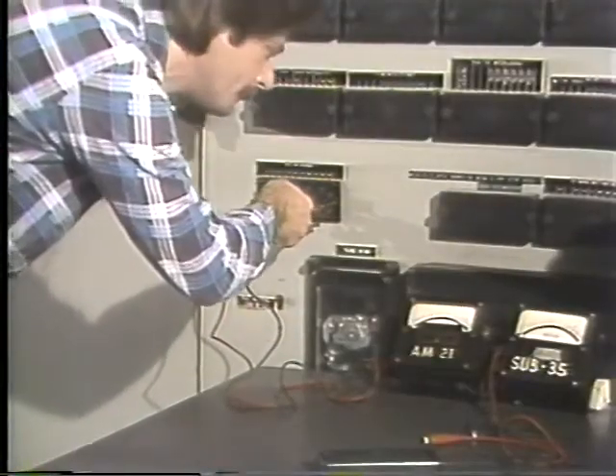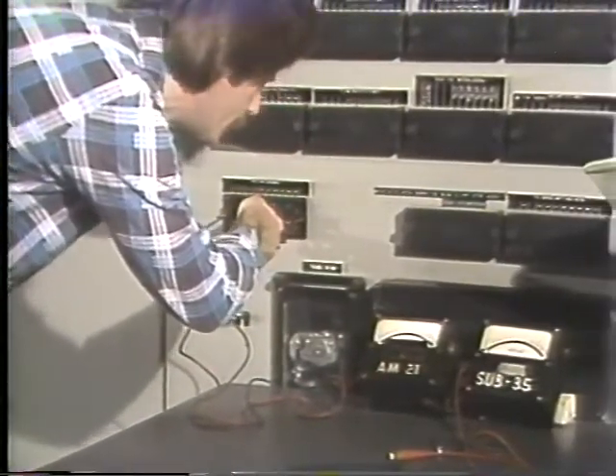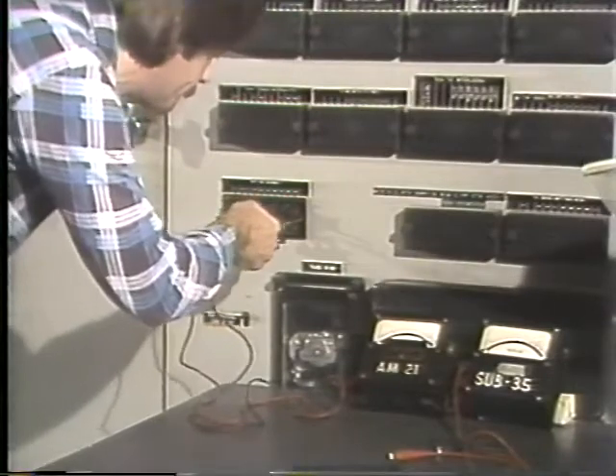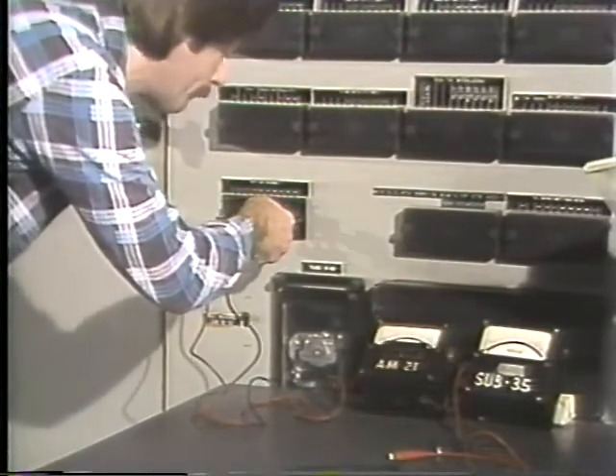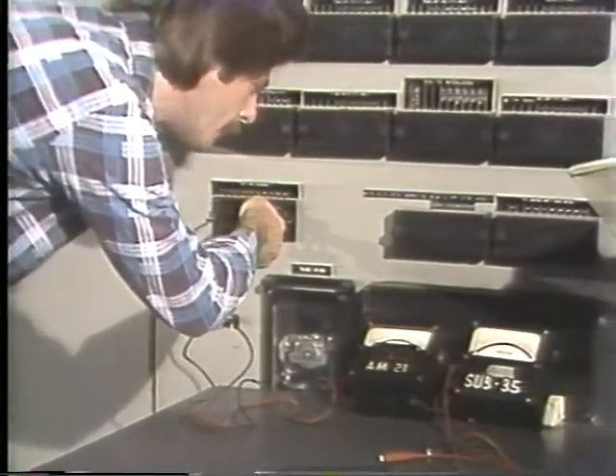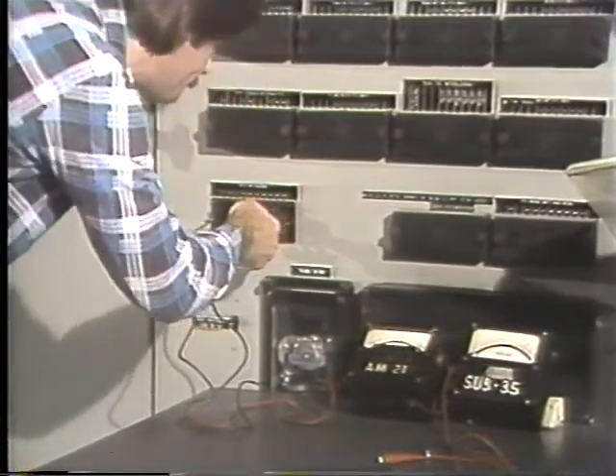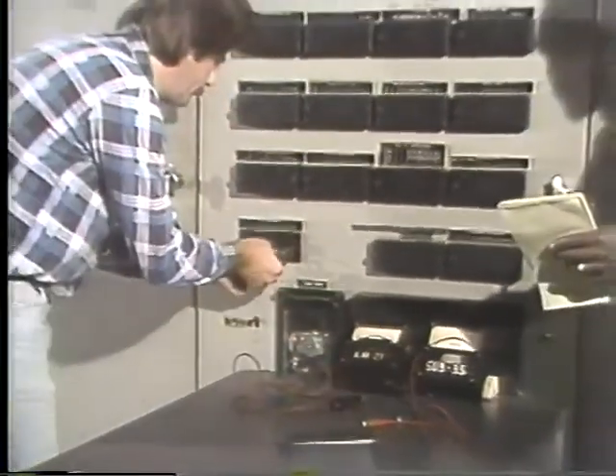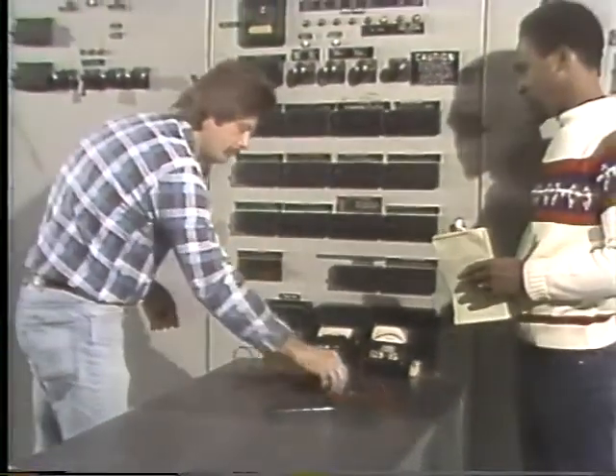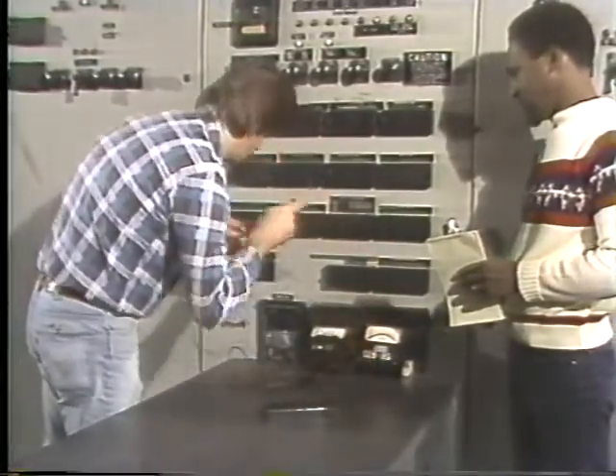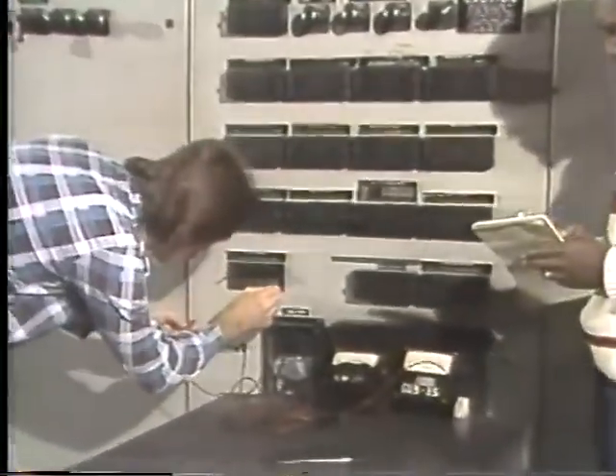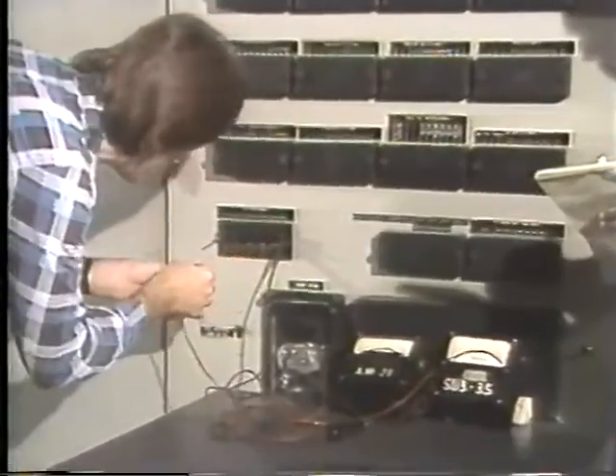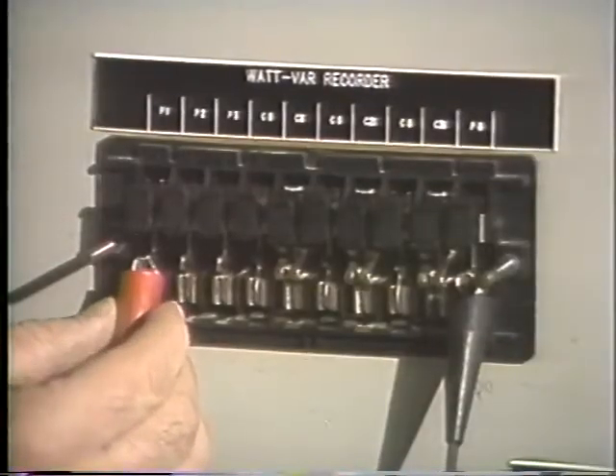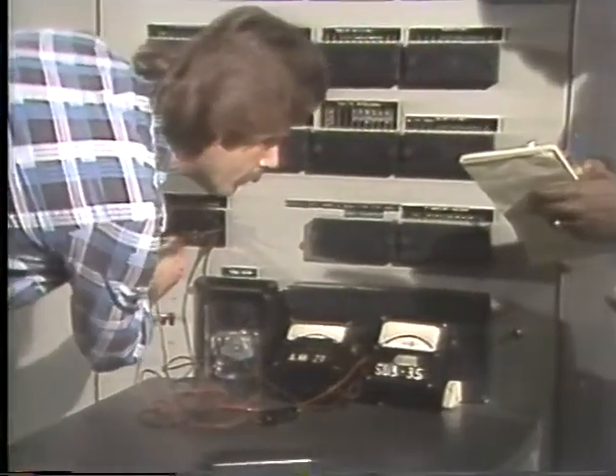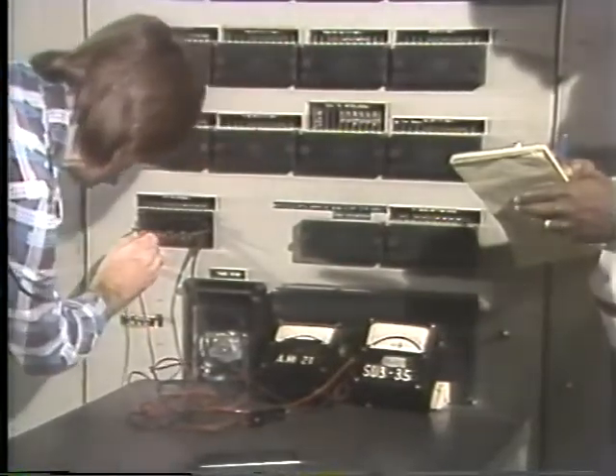As far as current transformers are concerned, that's the real safety point to remember. Don't open the secondary. If you have to remove an ammeter, de-energize the line or short the secondary so it's never opened. Taking voltage readings is a different story. You never have to open a circuit. All you have to do is measure each phase parallel to ground, or measure phase to phase.